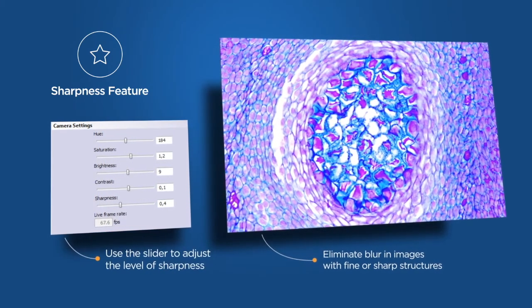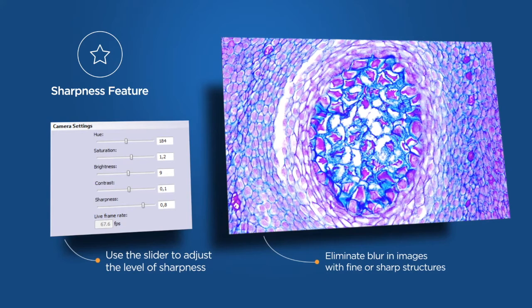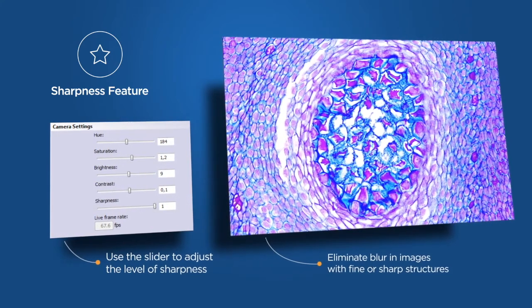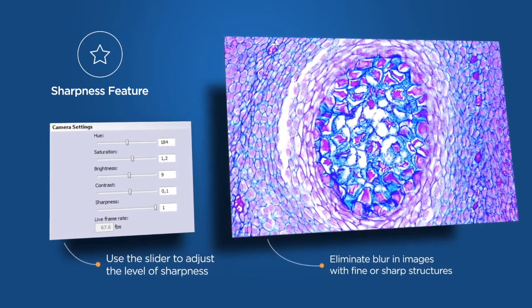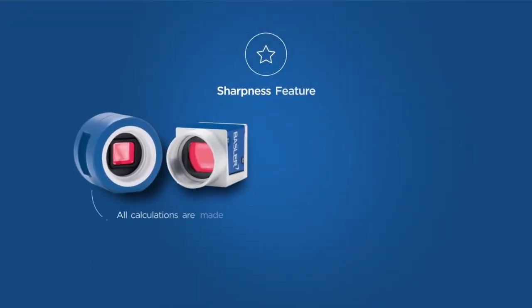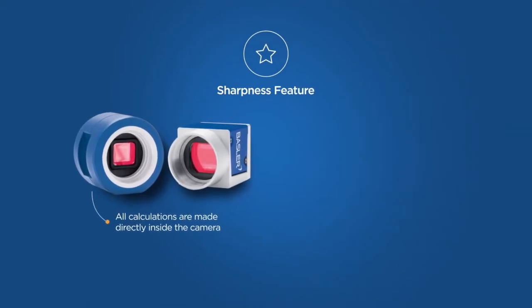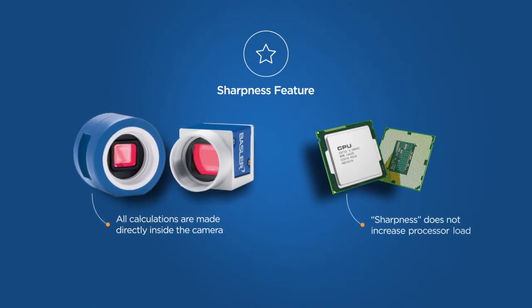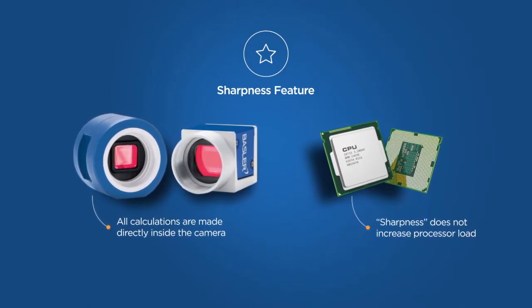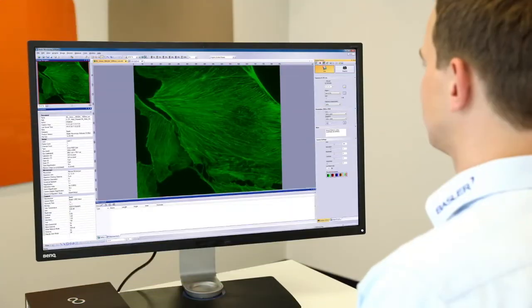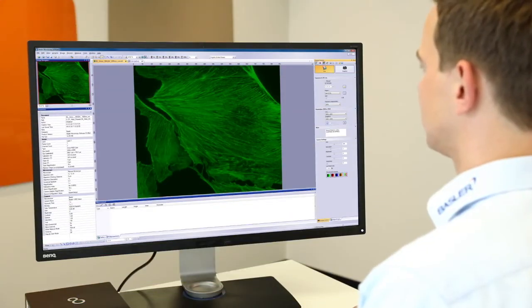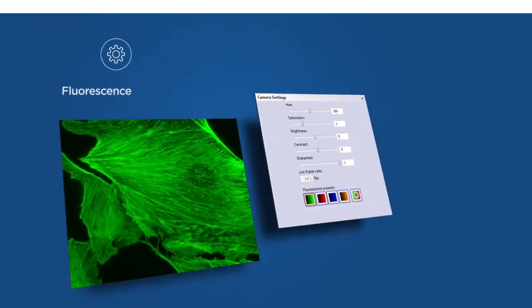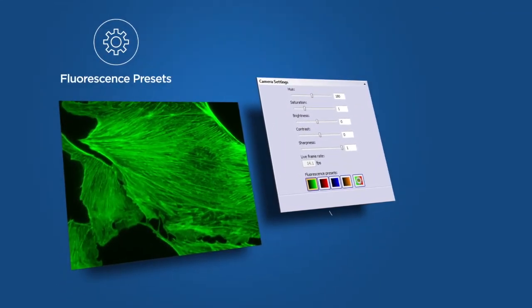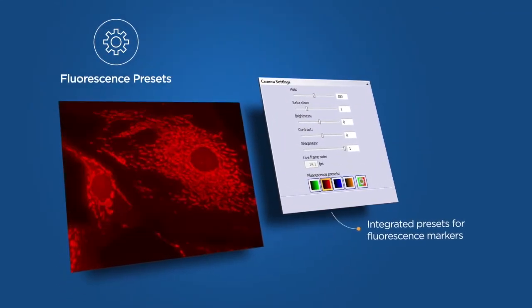Simply adjust the level of sharpness by using the sharpness slider. You can see the results immediately in the live view. Since all calculations are made directly inside the camera, this feature does not increase your processor load. To make your fluorescence imaging more convenient and to save you valuable time, Basler has integrated color presets for the most common fluorescence markers.